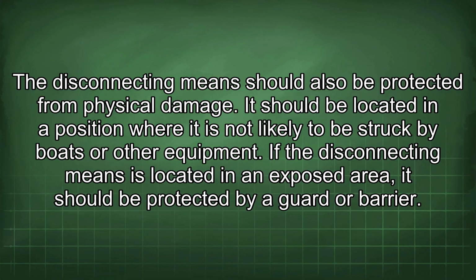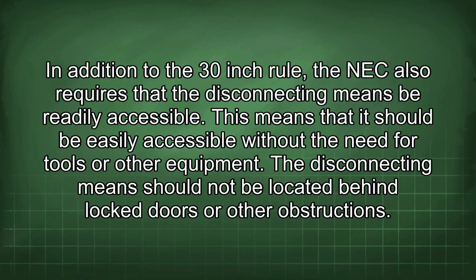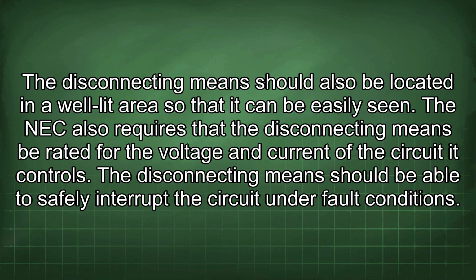The disconnecting means should also be protected from physical damage. It should be located in a position where it is not likely to be struck by boats or other equipment. If the disconnecting means is located in an exposed area, it should be protected by a guard or barrier. In addition to the 30-inch rule, the NEC also requires that the disconnecting means be readily accessible. This means that it should be easily accessible without the need for tools or other equipment. The disconnecting means should not be located behind locked doors or other obstructions. The disconnecting means should also be located in a well-lit area so that it can be easily seen.